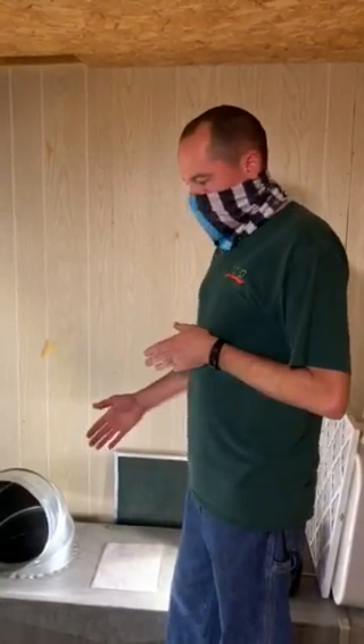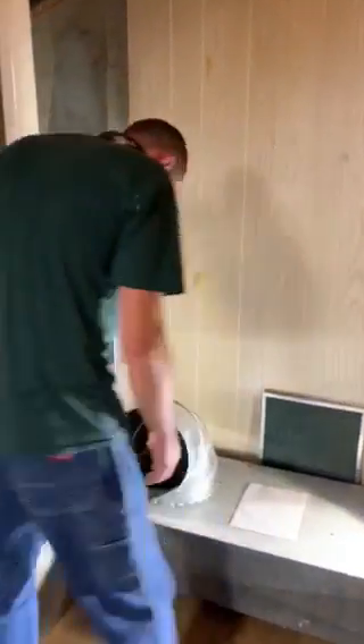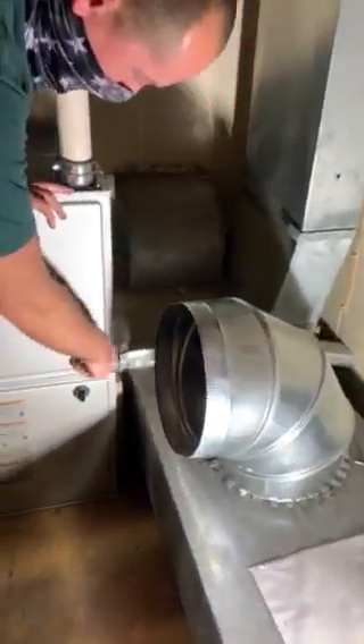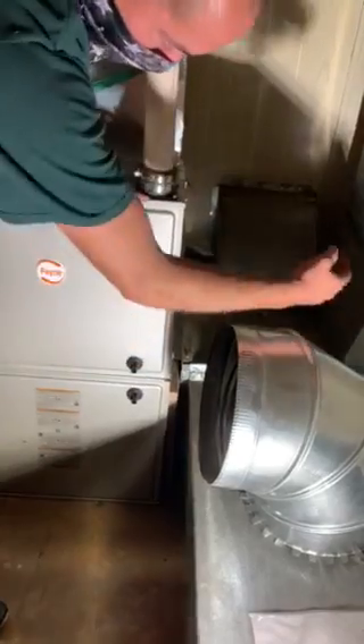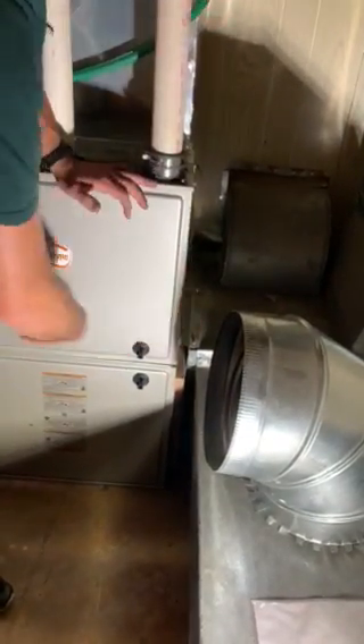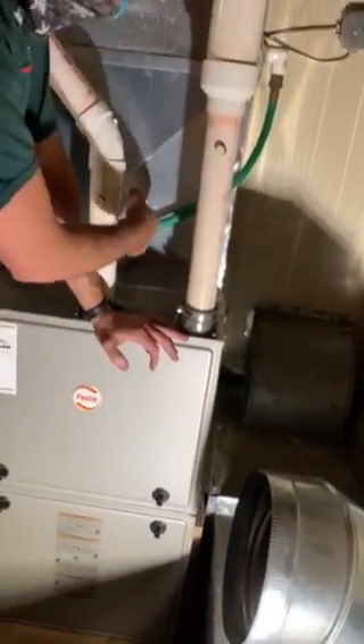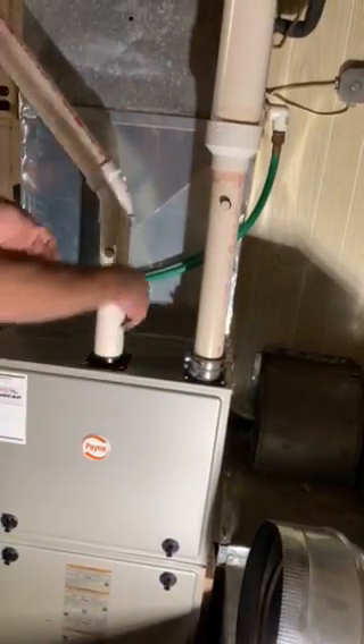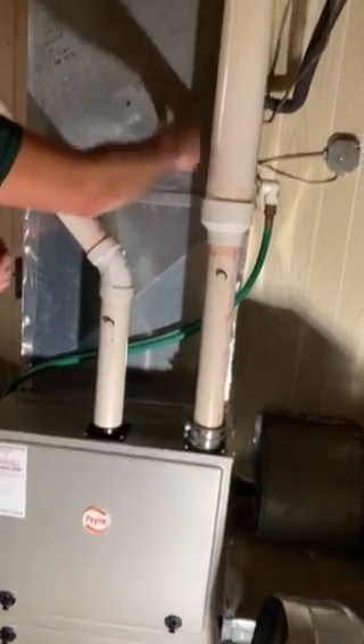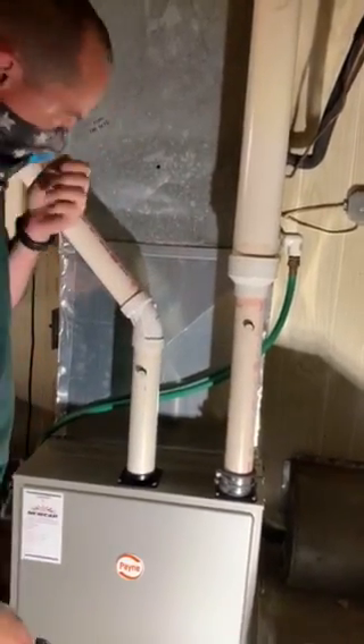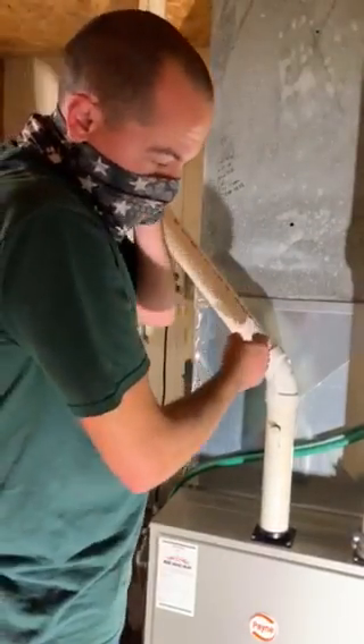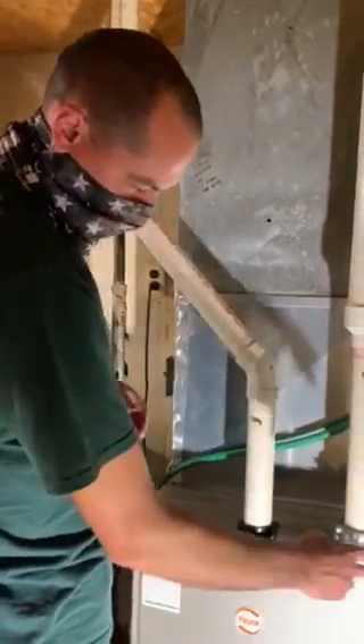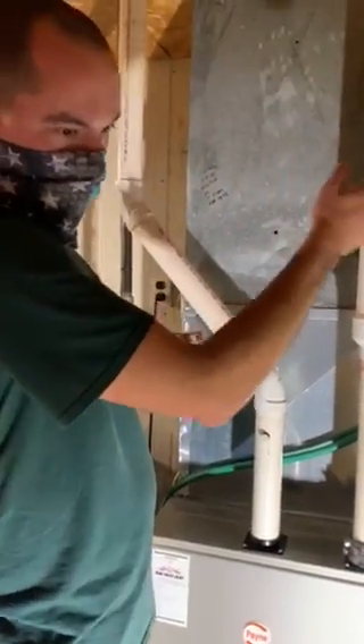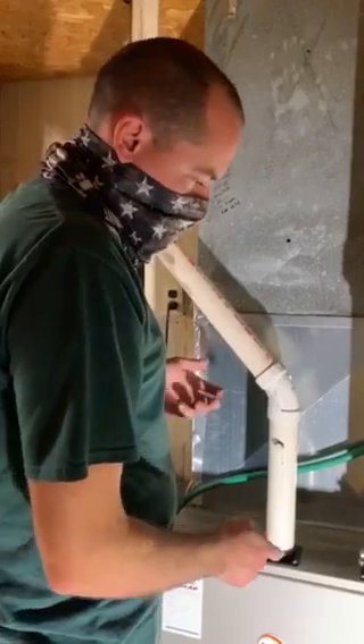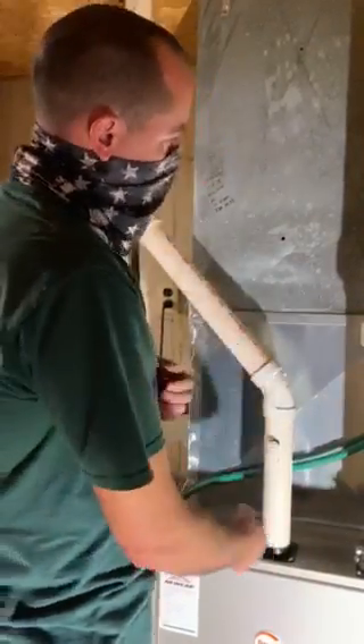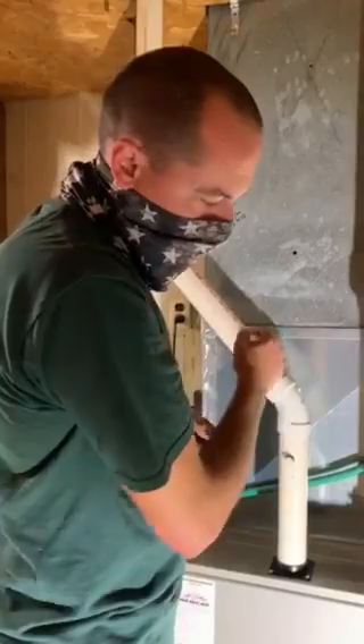Like this one right here, somebody installed a filter that's too short for the opening, so right now it's allowing dust to get through into the heat exchanger, and there's an air conditioning coil up there. Having too small of a filter will allow dust to get up and eventually plug that coil. Once that coil gets plugged, you won't have enough airflow across it, and your air conditioner could freeze up. Not only that, you can overheat your heat exchanger because you don't have enough air flowing through that coil.